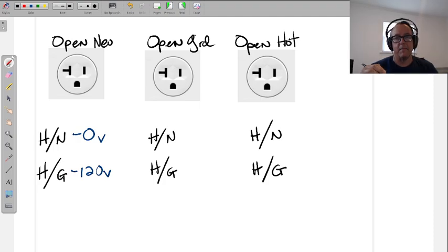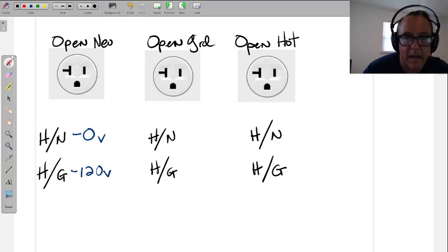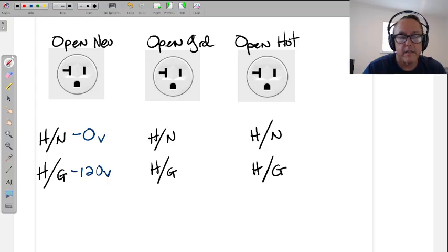Check breakers. Somebody earlier, by the way, good thinking, I believe it was Mr. Lindsay, who said, I don't see GFCIs. Very good. We're in a kitchen. That is a good thing to keep in mind. If I'm in a kitchen and I don't have power somewhere, before I go to check the breaker, let me do a quick scan and see if there's a GFCI that's tripped. All right, easy first, then we go down the road. That's why for continuity, no, not yet, because continuity requires taking things apart, getting up in attics sometimes, going to grab ladders, tools, etc. Not that we don't do that, but we try to go to the easier routes first before we start to get into deeper waters.